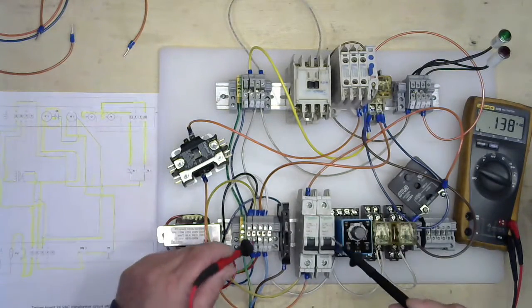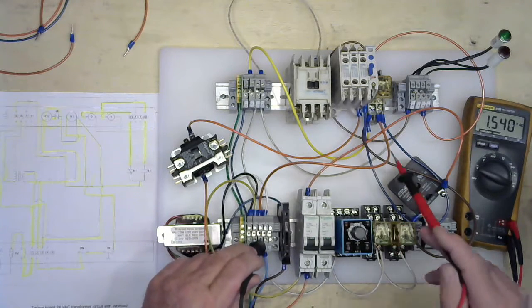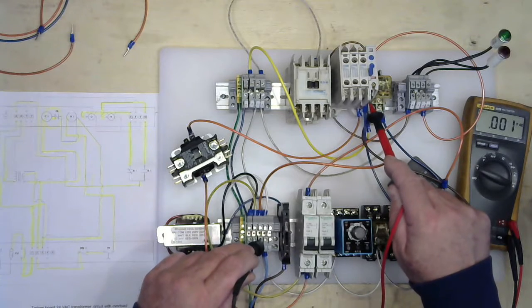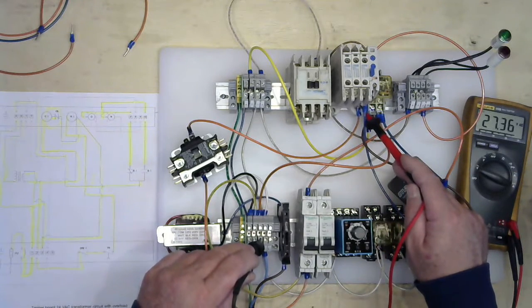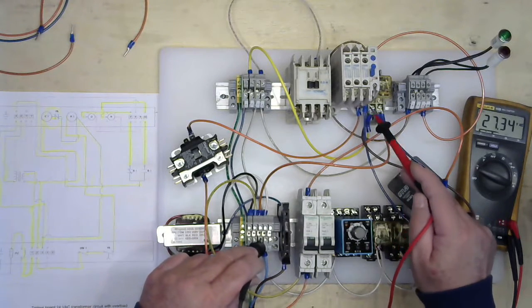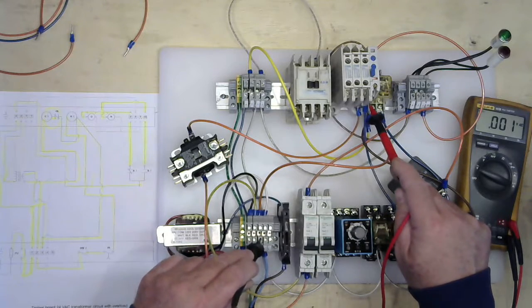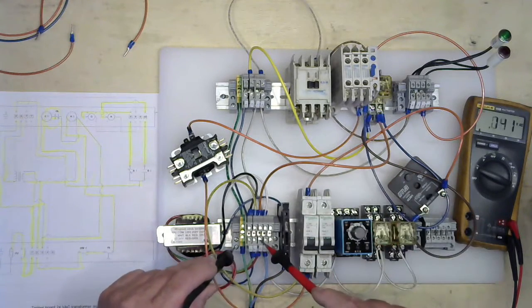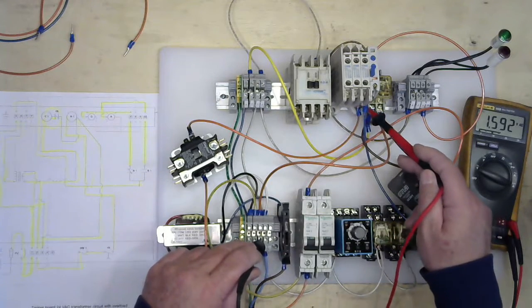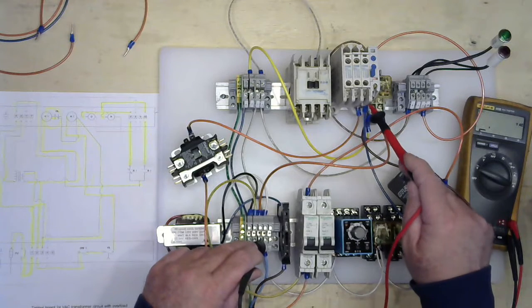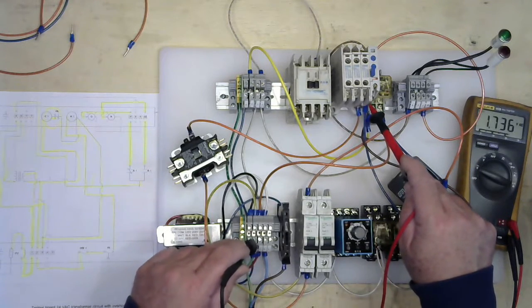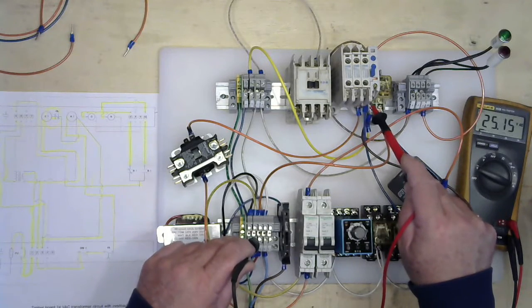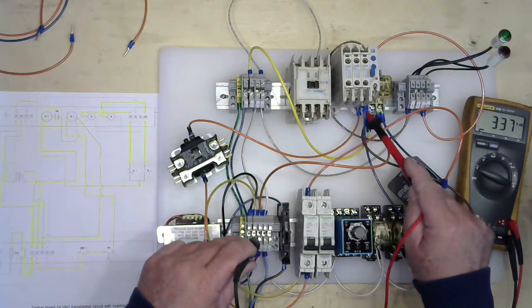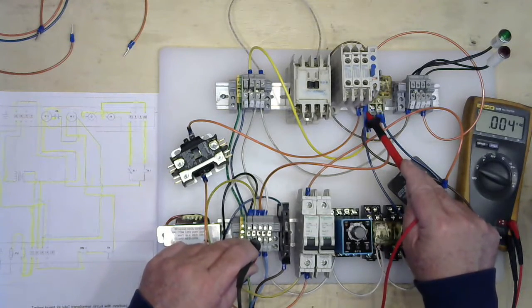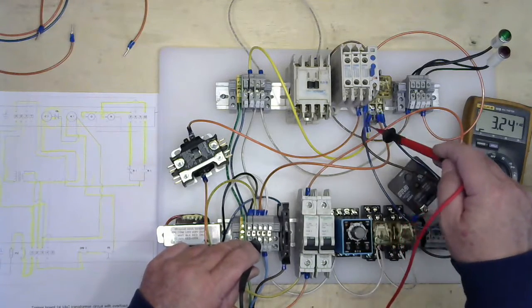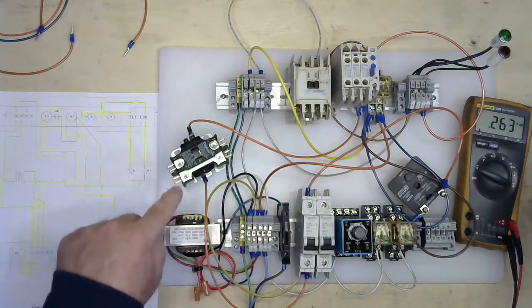And to verify that, I'm going to put my meter leads in my neutral again. I'm going to check it across my terminals. I'm getting 26 volts to terminal 95, and I'm getting 0 voltage to 96. And again, I'm coming from my neutral terminal, or my positive terminal, I should say. Positive to 95, getting power. Positive to 96, no power. I'll check it again from my neutral to 96. I'm getting voltage. Neutral to 95, I'm getting no power. So again, this is the wires coming back up, wires coming back through our lead here. Our contactor now is open.